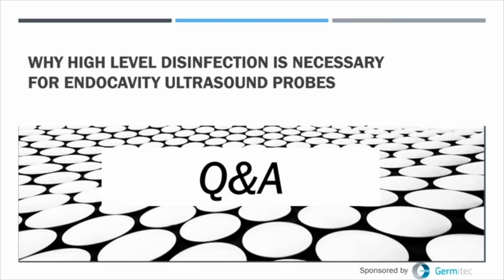That's the first issue. The second is it is almost impossible to physically remove a probe cover by pulling it off and have 100% assurance you're not contaminating the underlying probe. So if you have even gloved hands and you accidentally touch the probe cover to the probe as it's being removed, or your hands which have touched the probe or have touched the patient's mucous membranes now touch the probe, then you will contaminate it. And again, that's not visible. So one, the probe covers, and I've shown you the evidence, often fail.